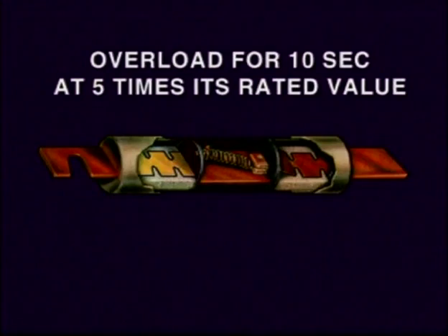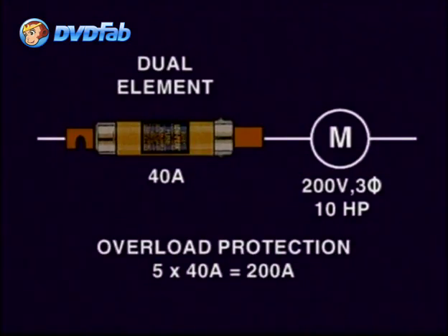If the fuse experiences a short-circuit overcurrent, the fuse will separate the links in the same fashion as the single element did. If the fuse experiences an overload condition for 10 seconds at about 5 times the value of the rated fuse, the overload element will snap out of the connector, thus disengaging the fuse from the circuit. This fuse allows motor protection from overloading. For example, if we had a dual-element fuse rated at 40 amps protecting a circuit of our 10-horsepower motor, we could sustain the overload inrush current of 193 amps at a little over 10 seconds before the fuse would open.